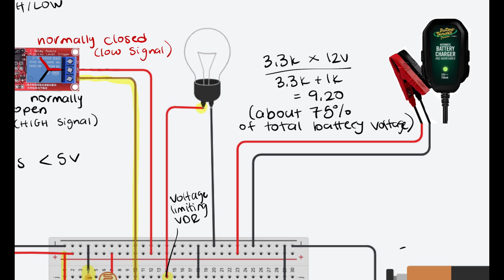The battery charger and maintainer is a very important component of this system. It connects the system to the grid and allows us to check for voltage drops and rises for grid disconnection and connection. It maintains voltage when the battery is fully charged, ensuring a fully charged battery at any time of emergency, and it charges the battery when the voltage drops below a full charge.